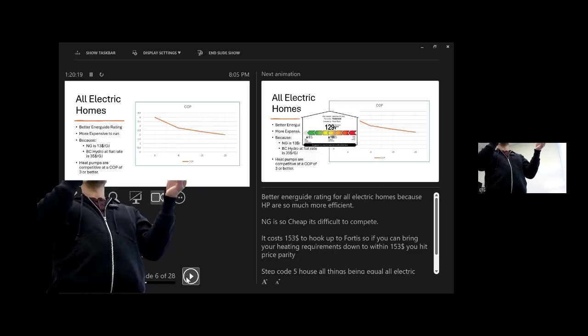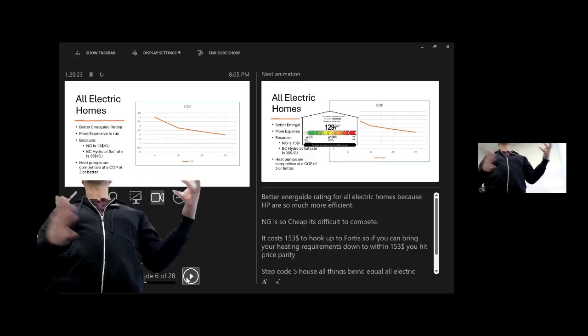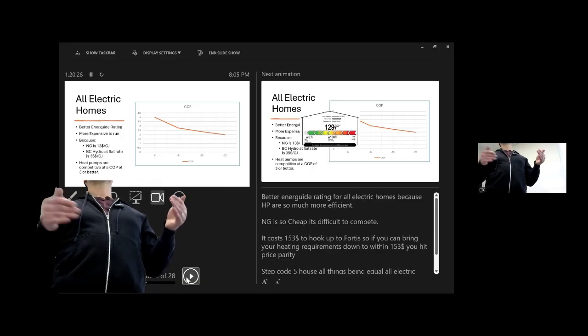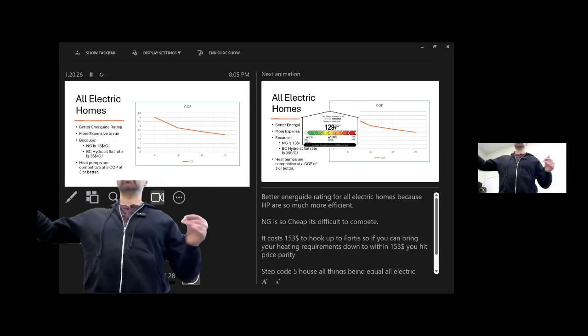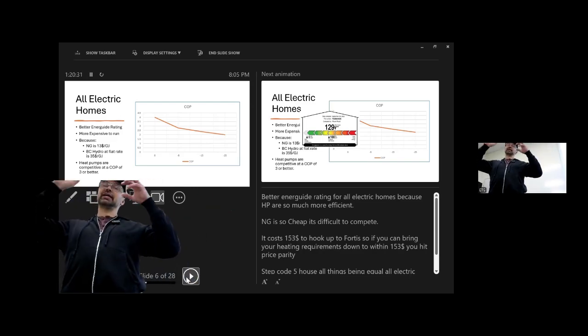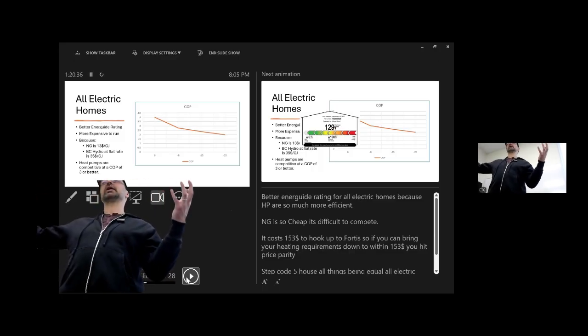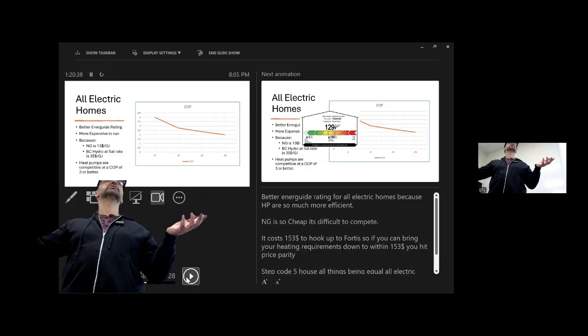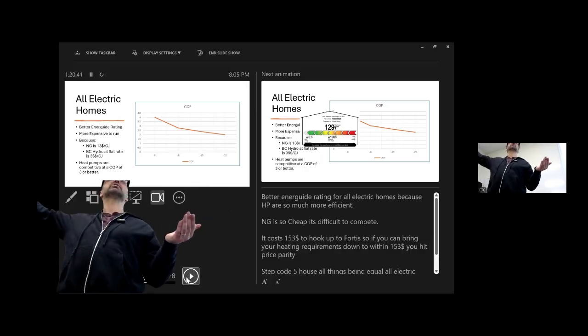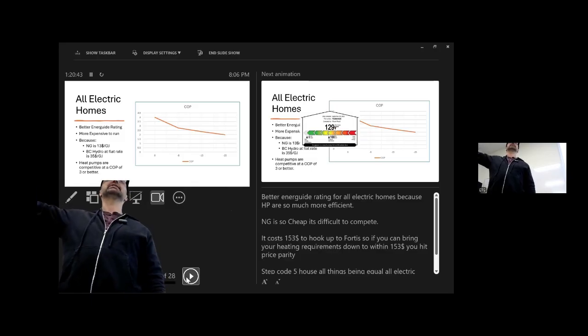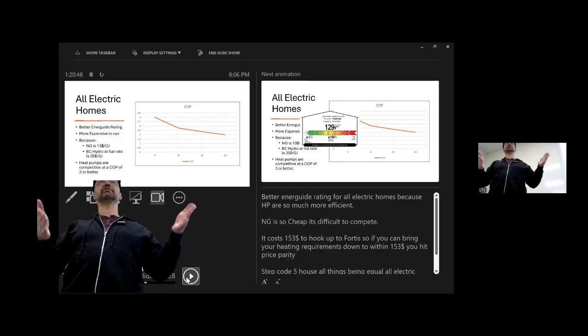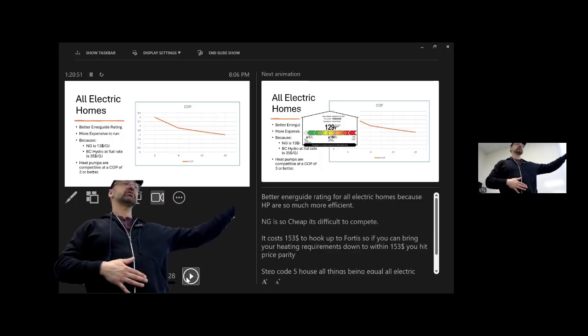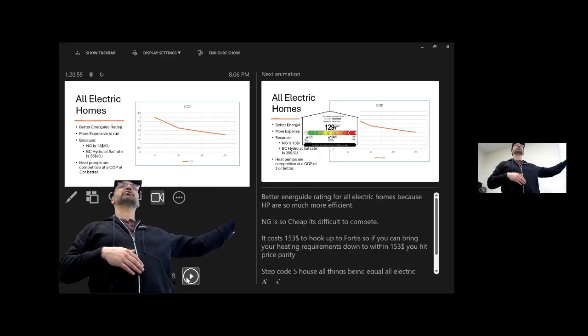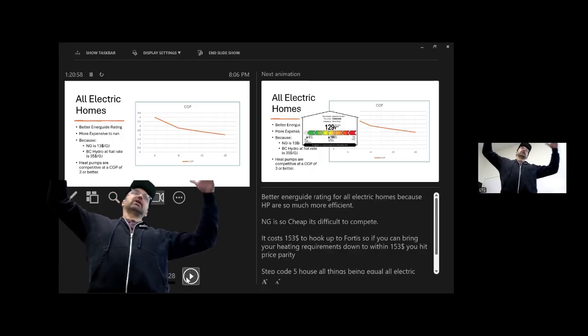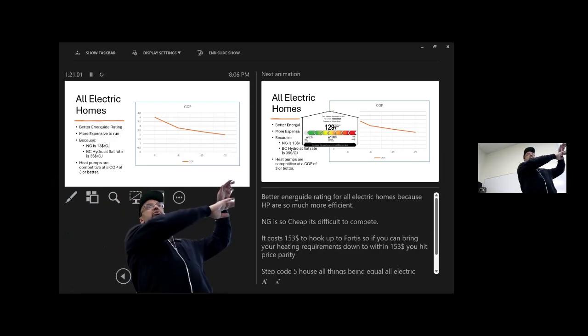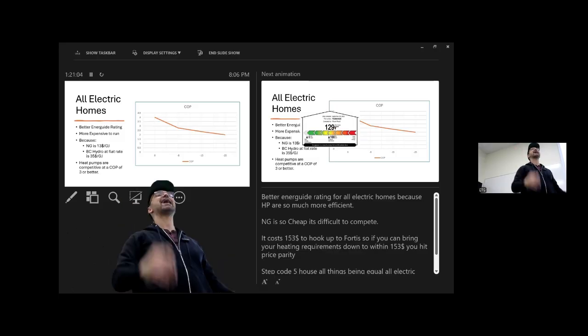And at some point, you want to just switch to resistance heating because you don't want to oversize your heat pump too much. That's where it gets quite confusing: you'll have a heat pump that can put out, let's say, 4 tons or whatever, so that'd be 50,000 BTUs, but that's at 8 degrees. You don't need 50,000 BTUs at 8 degrees. You need 50,000 BTUs at minus 33, which is the design temperature for Prince George. So that Arctic heat pump is only going to be putting out whatever, 20,000, or half of what you're needing.